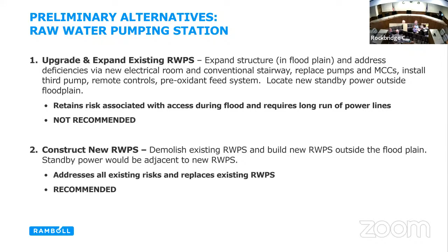But the issue is we'd still be in the floodplain. Do we really make a significant investment in new infrastructure and still keep it in the floodplain? Our recommendation is no. Instead, we recommend demolishing the existing raw water pump station and building a new one outside the floodplain, allowing us to bring standby power to the building and address the existing risks identified during the condition and capacity assessment.